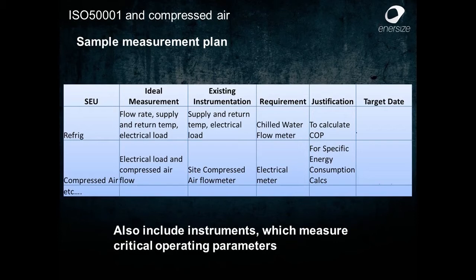The next one is compressed air. Maybe we will say that the ideal measurement is electrical load and compressed air flow. Let's say we already have a flow meter, but we need the electrical meter. What we need to measure here is specific energy consumption as a key performance indicator. It could also be the other way around, where we have the electrical meters but need flow meters and pressure profile in the system, or we may require all of them to get the data we would like to see.